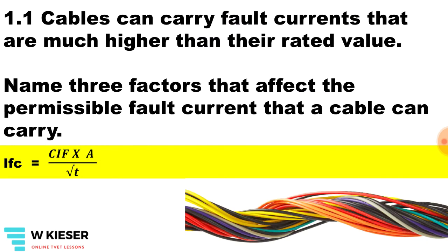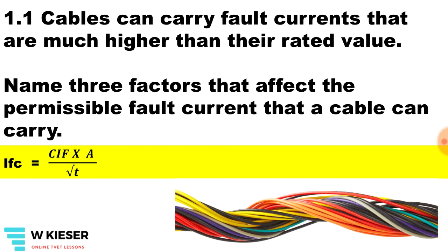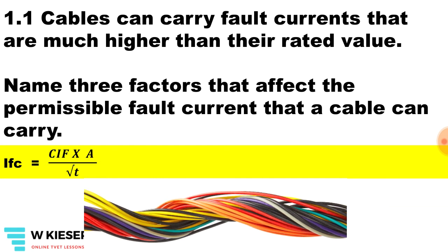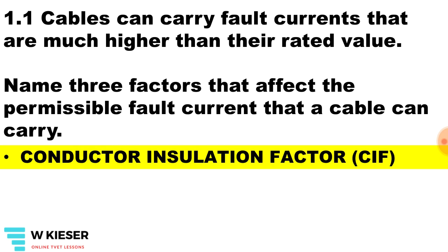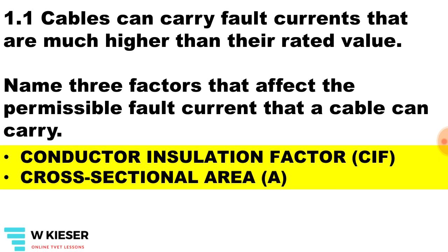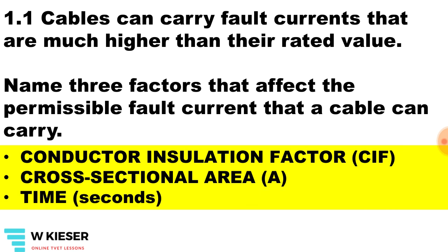Cables can carry fault currents that are much higher than their rated value. Name three factors that affect the permissible fault current that a cable can carry. Here we've got the formula to help us answer this question. We will need to know the conductor insulation factor, the cross-sectional area, and the time that the current flows.